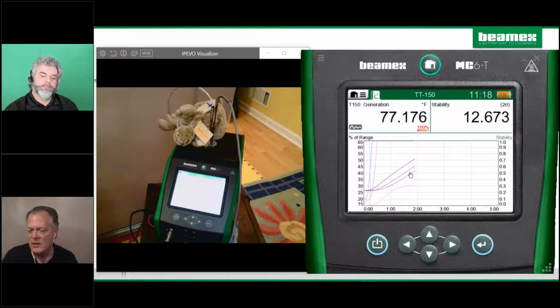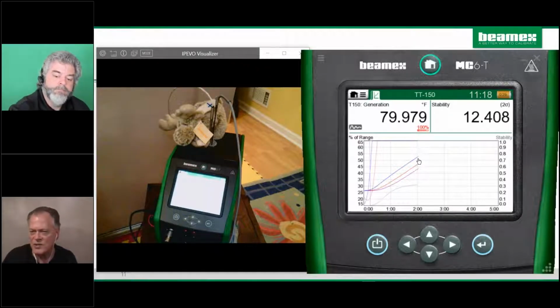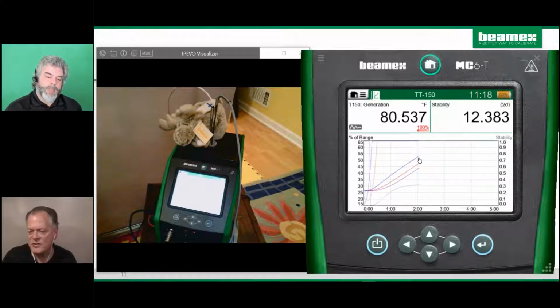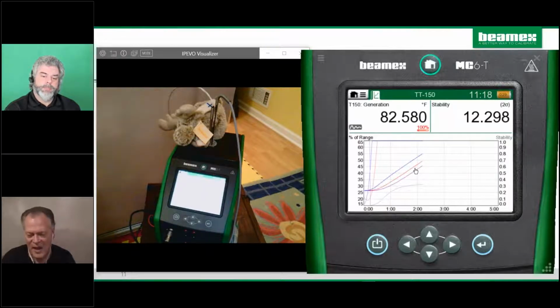So, you know, with a dry block, the internal sensor is mounted very close to the heat source, and it's a small mass. My reference probe, the red line, is a 1/4 inch diameter, so it takes more energy and more time for it to reach this temperature that this guy is sensing. And plus that insert has to heat up itself, and that's more mass. So that does make sense.